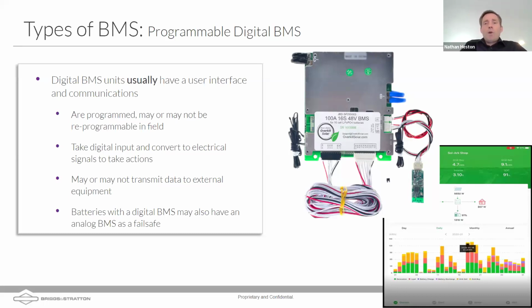All those wires hanging down in the center are what are called balance of system wires. They balance cell voltages to make sure all 16 of those cells are at the same states of charge. It can take digital input and convert it into electrical signals to take action. So this BMS is capable of being controlled, and it's capable of outputting digital signals as well.